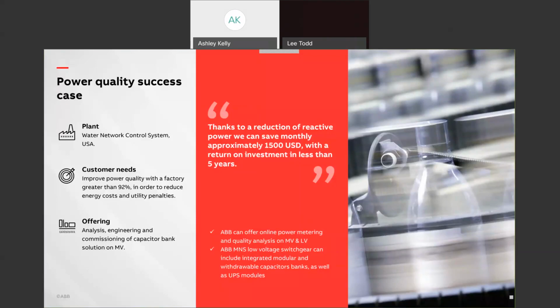The local service team in that state provided them a detailed analysis of all the issues, which resulted in the installation and commissioning of a medium voltage capacitor bank. This analysis and installation saved the customer around $1,500 a month, giving a return on investment of less than 5 years, as well as improving sustainability and power consumption on the site.